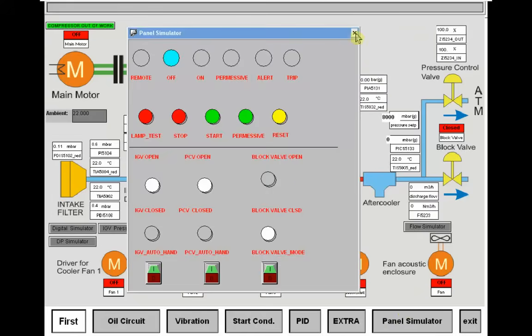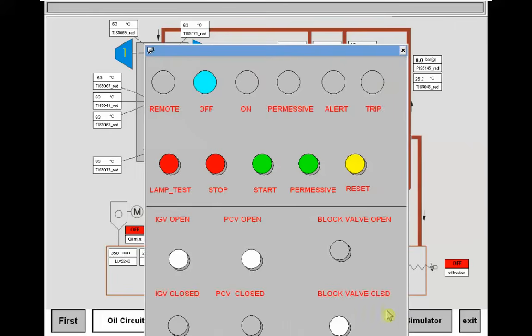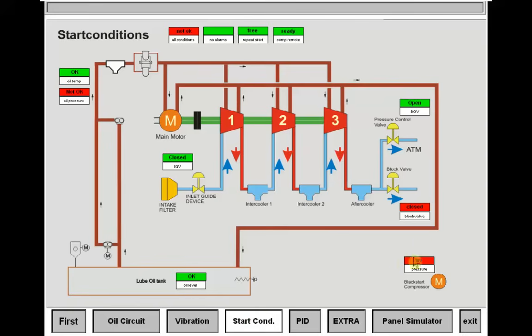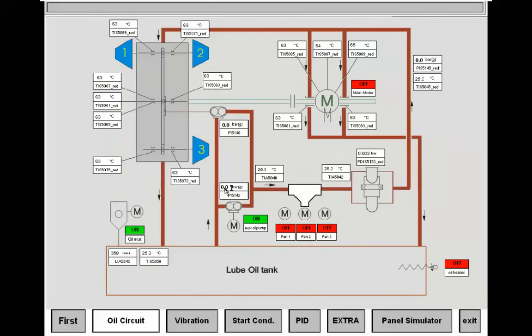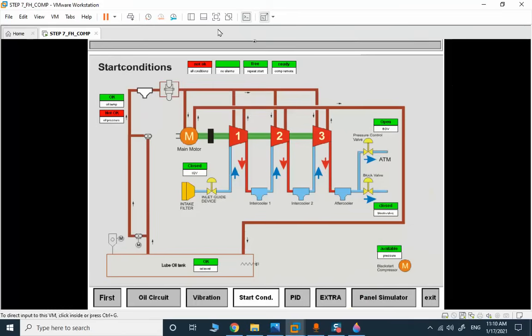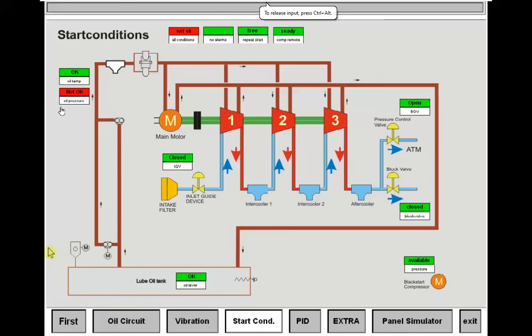The next function test: consider that we want to start the compressor by clicking the permissive, but we don't have enough pressure here. In the permissive mode — which is the start permission check — all conditions are checked here. You can go to start conditions, and all of these conditions should be green. If you don't have enough pressure here — because the auxiliary oil pump is running — that is one of the main conditions that is not met. If the oil pressure is not sufficient, you cannot start the system.